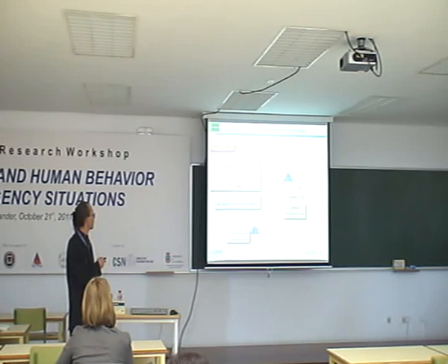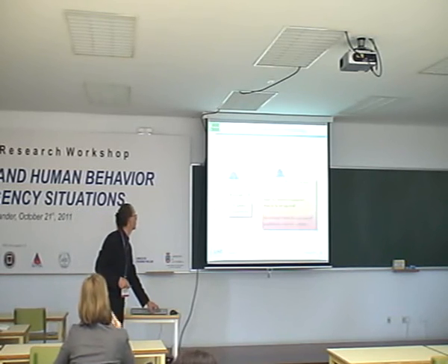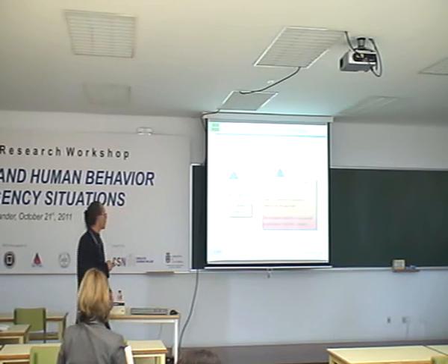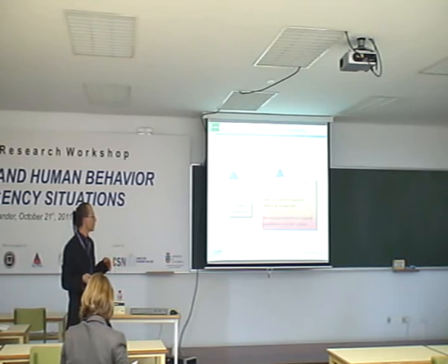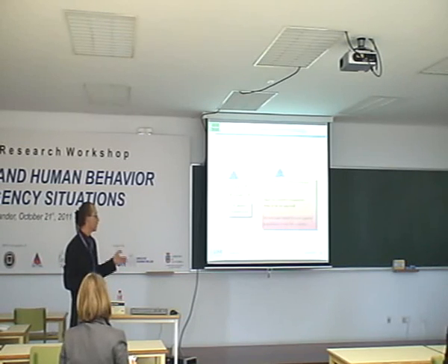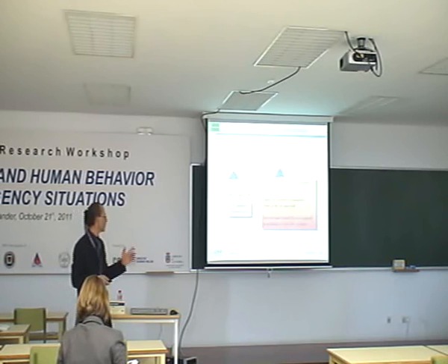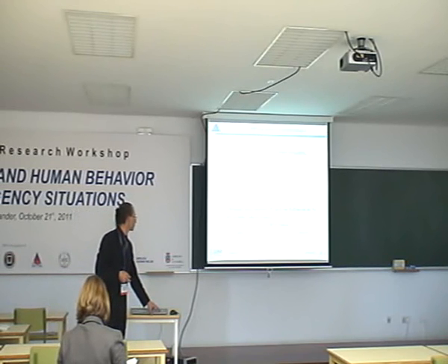With the CFD calculation and the evacuation scenario, we get an exposure scenario. From those exposure scenarios, we can calculate the time to complete evacuation and the time to be incapacitated through FED, FEC. This is done for each individual of each exposed population of each fire scenario.